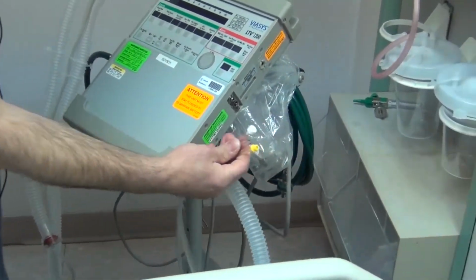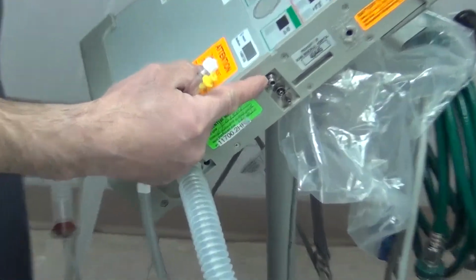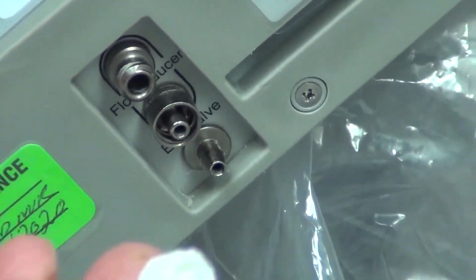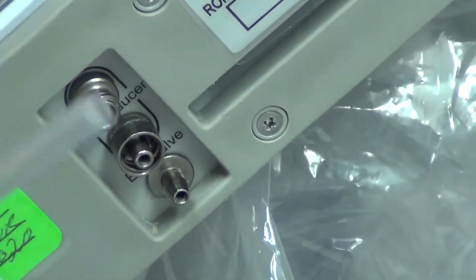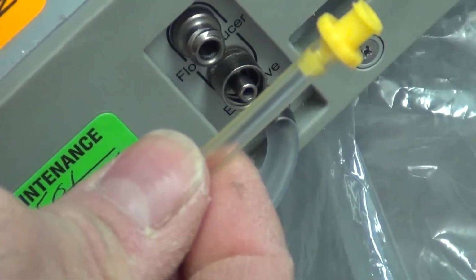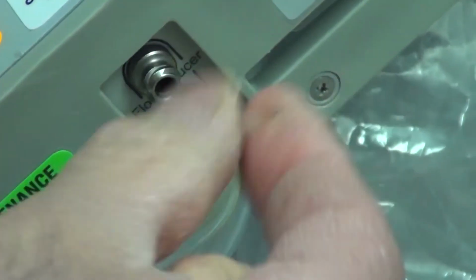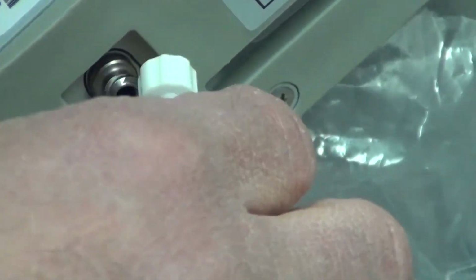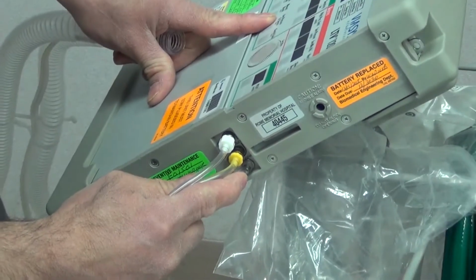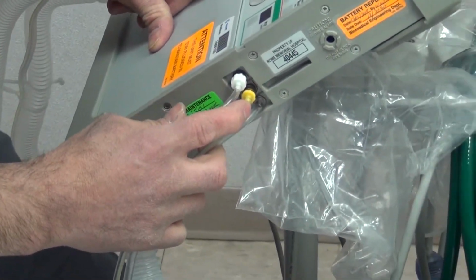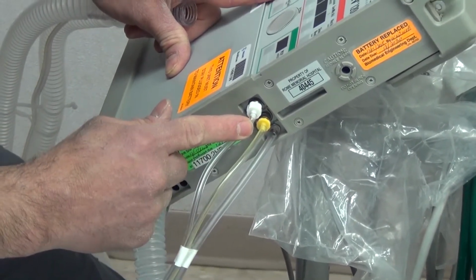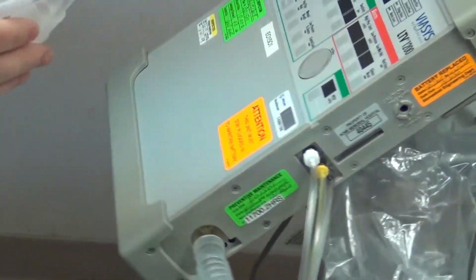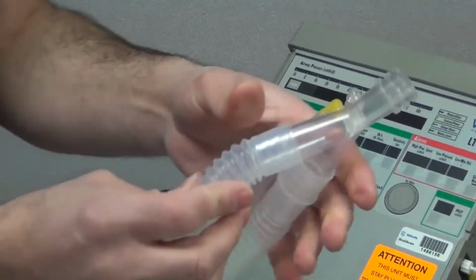Next, you want to connect these little tubings, and if you look just a little bit up, you'll see here that you have those three little ports. They are all different, so you cannot mistake which one you do. This one goes to the bottom. This one goes in the middle. And notice I am screwing them in. This one goes to the top, and this one also will have to be screwed in. So the first one is push. The middle one, the yellow one, you screw in. And the top one, the white one, you screw in. The circuit is now connected to the ventilator.